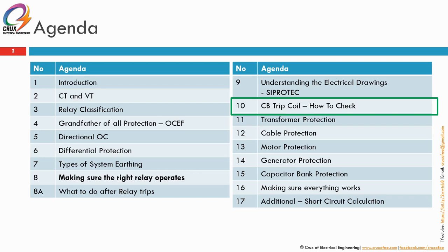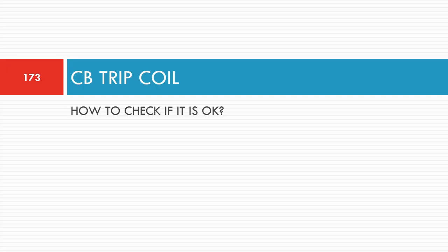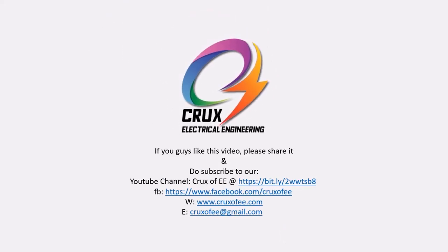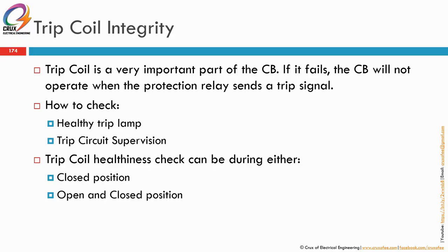So how can we check the condition of the CB trip coil? How do we check if the CB trip coil is okay or not? So CB trip coil is a very important part of the circuit breaker. If it fails, the circuit breaker will not operate when the protection relay sends a trip signal. So this is the worst thing, or the last thing, that we want to happen lah. We don't want this to happen lah.